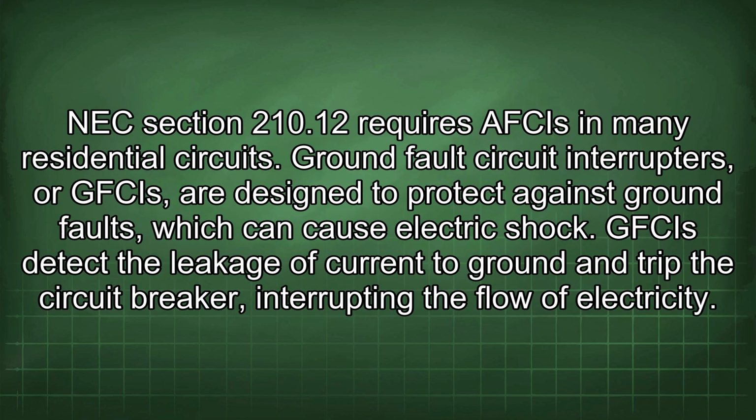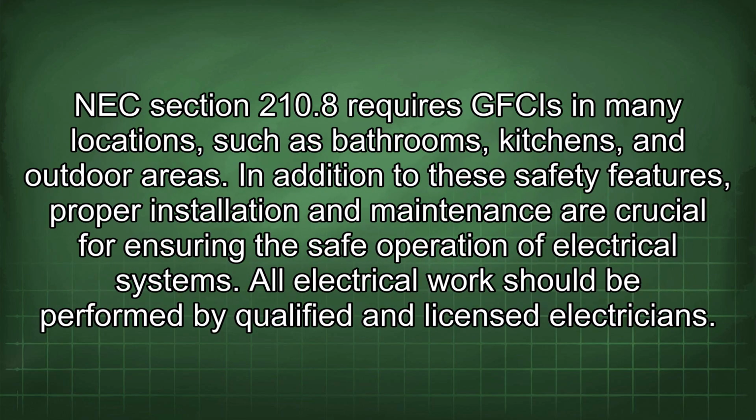NEC Section 210.12 requires AFCI protection in many residential circuits. Ground fault circuit interrupters, or GFCIs, are designed to protect against ground faults which can cause electric shock. GFCIs detect the leakage of current to ground and trip the circuit breaker, interrupting the flow of electricity. NEC Section 210.8 requires GFCIs in many locations, such as bathrooms, kitchens, and outdoor areas.